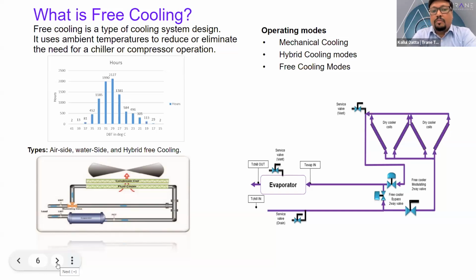Now the question comes: can we combine free cooling with the chiller unit into one? The answer is yes, we can definitely combine free cooling and the chiller into one, and that's commonly referred to as a hybrid chiller. And what is a hybrid chiller? A hybrid chiller is a cooling system that incorporates both a chiller and a free cooling system in a single package. The system is designed to take advantage of the free cooling potential of the ambient air when the outdoor temperature is low enough to provide sufficient cooling, and to switch to mechanical cooling when the outdoor temperature rises. That happens through a modulating valve, depending on the manufacturer.